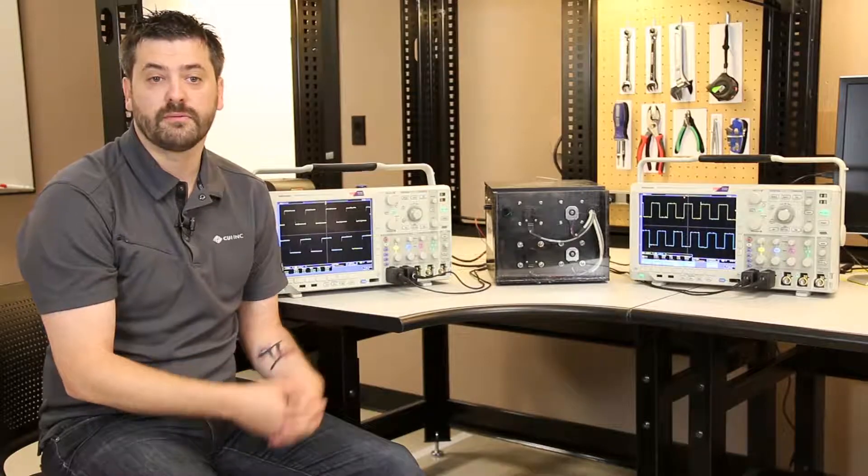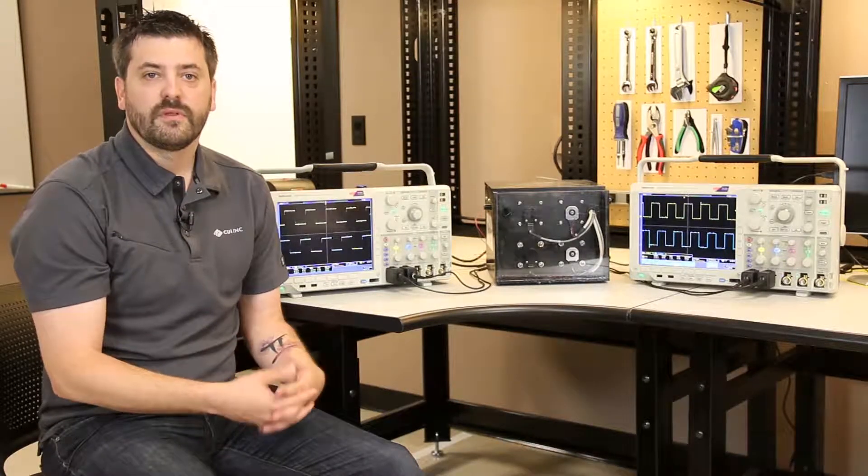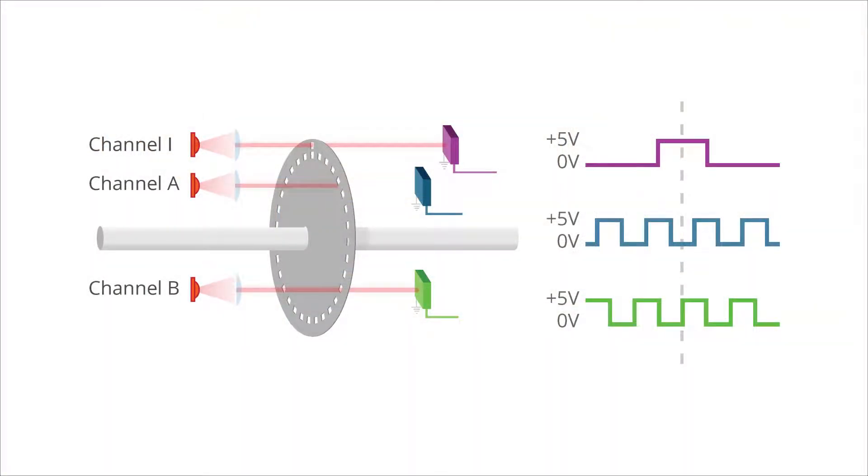Unfortunately, this is one of the areas where optical encoders fall short, particularly with the dust, dirt, and oil in the environment. Optical encoders require line of sight, and if it's a dirty or dusty environment or a lot of oil in there, that can drastically influence the performance of that optical encoder.